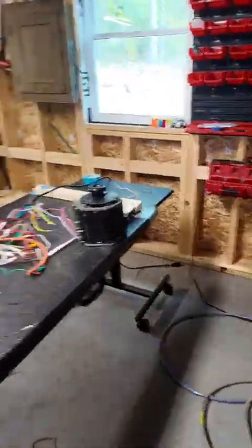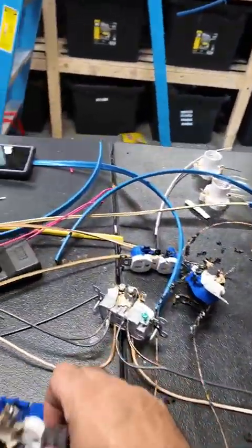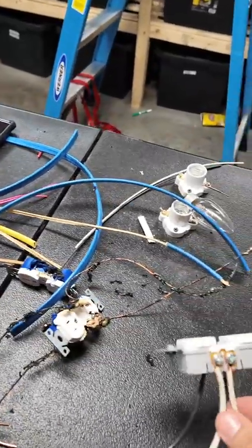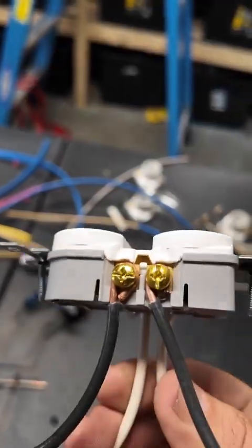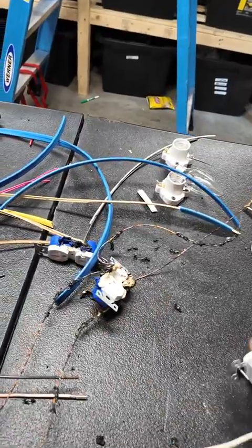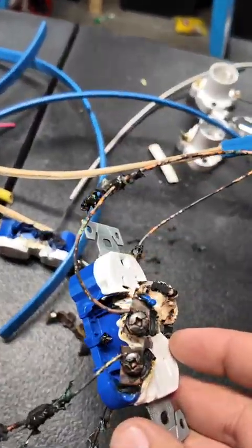Watch, I'll show you. Let's go into my shop — it's trashed — but here are some of the other results of experiments. This one did 15 minutes of 90 amps with hooks instead of backstabs, and that's 10-gauge. This one was hooks, this one was hooks.